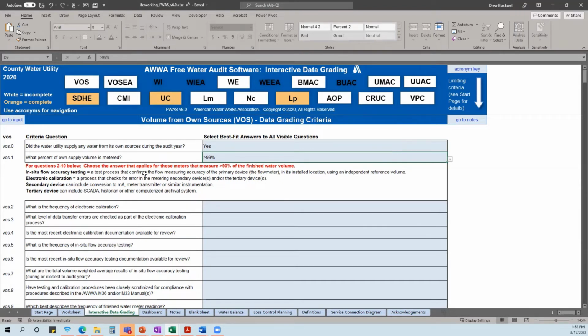And just a quick question about that one. That would most likely be a weighted average as well, because looking at our system with the 3 wells, not all those wells produce the same amount of volume. Right. Okay. Right. Yep. So we're looking at the percent of the supply volume. That's a great distinction, Nicole. So in that scenario I gave you with your system, it's not the percentage of meters, but the percentage of the volume that's metered.